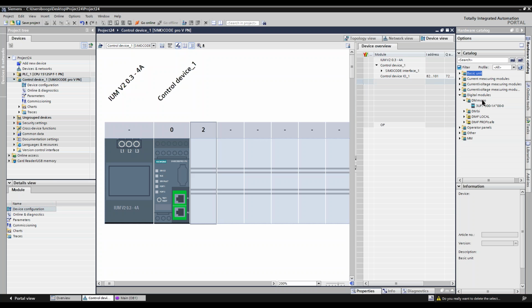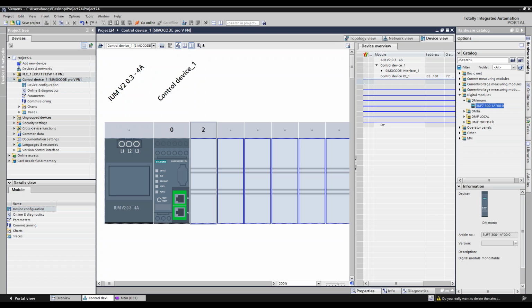Now the difference here, mono versus bistable. Mono means that it is a contactor. If it's a normally open contactor, then you put in a normally open contactor. It is energized closed, but if somebody takes the power away, then it returns to its normally open state when the power comes back. The bistable digital module means it has retentive memory. If it's a normally open contact, energized closed, but then the power goes away and comes back, it returns to the state that contactor was at. If it was closed, even though it's a normally open contact, it returns to that closed state. It retains its memory of where it was at. It has a retentive memory in it.